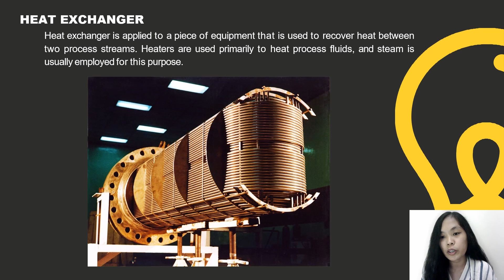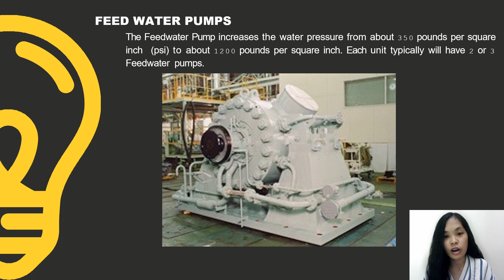Moving on, we have the feed water pumps. The water level in the steam generator and the nuclear reactor is controlled using the feed water system. So the feed water pump has the task of taking the water from the condensate system, increasing the pressure, and forcing it into either the steam generators or directly into the reactor vessel. So the system of feed water pumps usually contains 3 parallel lines of feed water pumps with common suction and discharge headers.